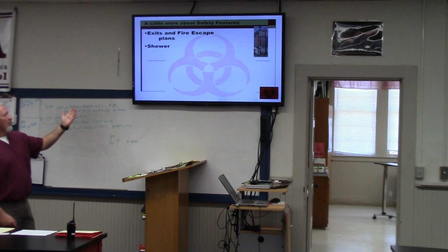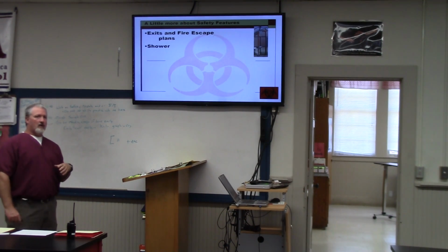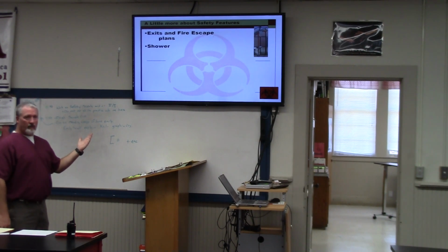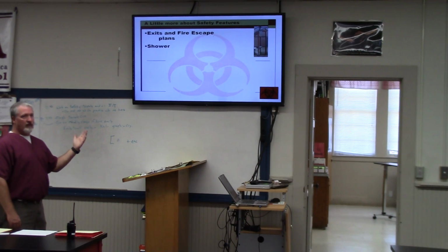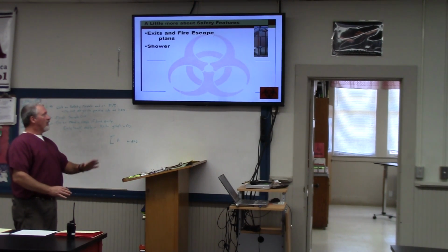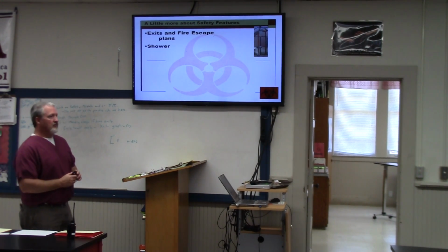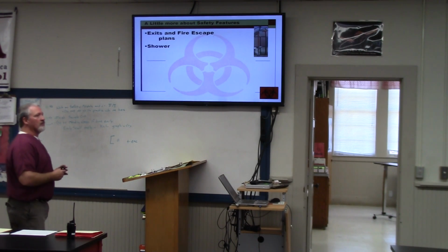The safety shower, we don't have to have one in here because we don't have advanced chemistries in here. You have to have one in the chemistry department and the biology department because they have advanced chemistries, formaldehyde, all sorts of things. So it's something where if you pull the lever, it's easily accessible, there's no obstruction. When you go up there and you pull that lever, it will douse you with water continuously for 15 minutes straight. Okay? And try to get all the hazardous chemicals off.